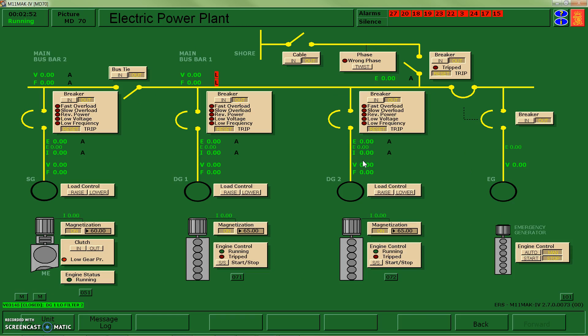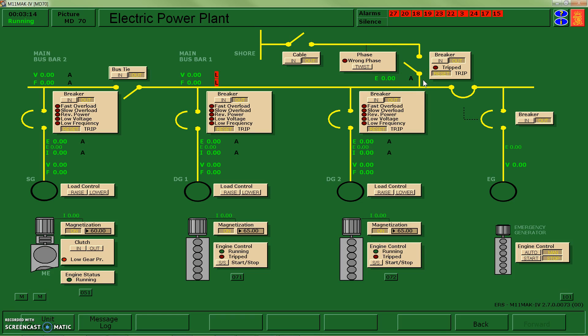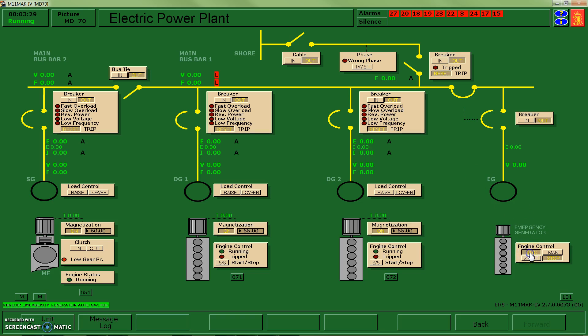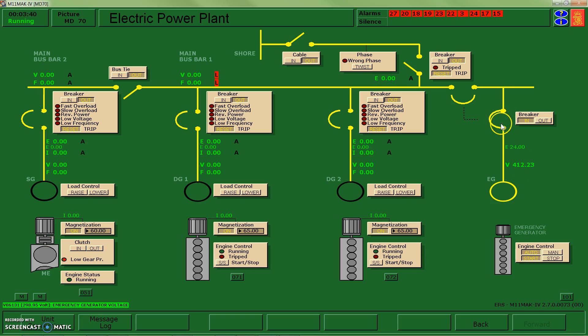I'm going to go to my electric power plant page, number 70. I have a couple of options here. I have a shore power connection - consider that a glorified extension cord plugged into the wall to provide power. The problem is that it just isn't going to have a lot of capacity; at some point operating a few large pieces of equipment, some pumps, some air compressors, I'm going to overload that line. So I'm going to start up using my emergency generator, hitting auto. We can see it turns on, my voltage starts to increase, and the breaker connects in, sending electricity to my electrical system.